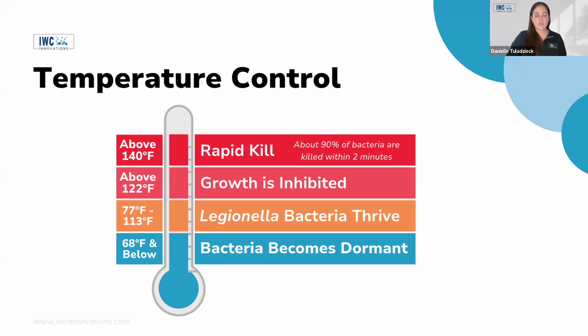So we need to maintain storage temperatures of at least 140. If 160 can be achieved, even better. Your target delivery temperature should be above 124 or at the maximum that your scald protections allow. A master thermostatic mixing valve will allow you to heat to this target, then down mix to your required delivery temperature. Also ensure that recirculating systems send the water back through the heating tank and not just mixed back into your cycle to reheat. Cold water should remain under 77 degrees Fahrenheit.